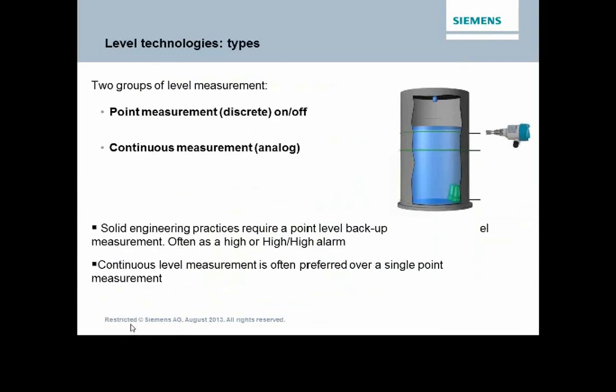Real quick here, for those who are fairly new to instrumentation, you'll hear some terms from discrete and analog measurements. Basically, a discrete measurement is a simple on or off measurement. We might see along this line here, which we do supply, but a lot more commonly it is used as an alarm, either a high alarm or a low alarm, or an input to a PLC to either turn something on or turn something off.